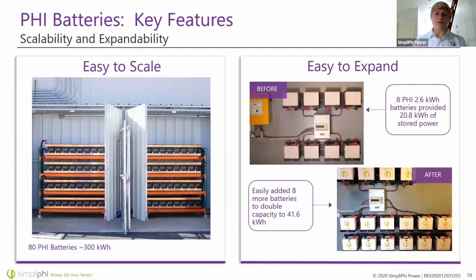Here are some photos of a scalable system. The system on the left is 80 batteries, that's over 300 kilowatt hours of storage. They're just wired all in parallel, with a big fat bus bar going over the top of the terminals. It's got 10 on each bus bar here at this airport hangar on the left, and each bus bar connects to another common connection point. We'll talk more detail about wiring later.